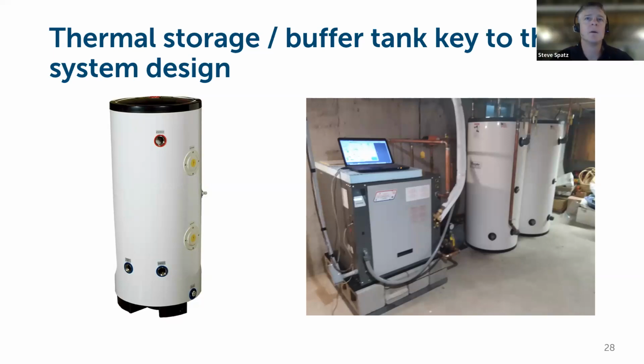Sure. I mean, there's a lot to that. Again, you're trying to integrate a refrigerant coil into an air handler that is designed around putting out 120, 130 degree air through the ductwork into the house from the fossil fuel system. And the heat pump will be putting out towards the lower end of that spectrum as far as temperature goes. And often that existing ductwork is hopefully designed around the capacity and the flows needed and the room by room needs of the fossil fuel system.